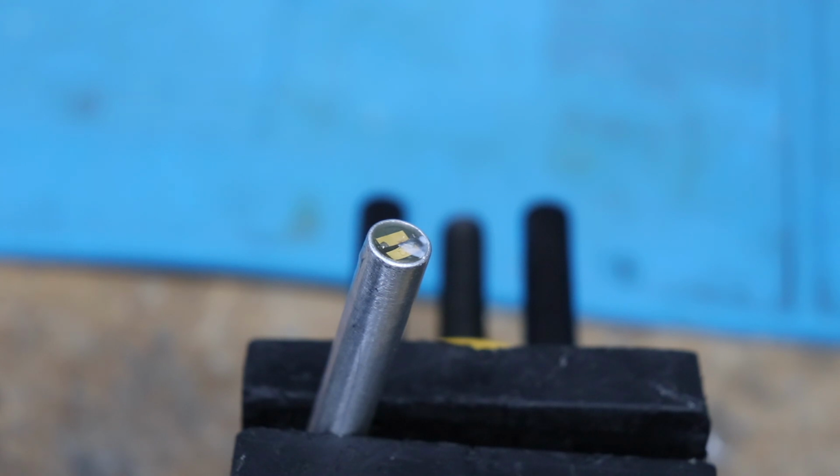You do get different frequencies. Just to give you an example, 8.2 megahertz or 8 megahertz is commonly used in vascular surgery for insonating blood vessels which are relatively close to the surface. So if, for instance, you were wanting to make up a Doppler machine, say for listening to a baby's heartbeat in pregnant ladies, then you wouldn't use this type of probe. The signal would get attenuated too quickly. So you go for something like a probe in the order of 2 megahertz.